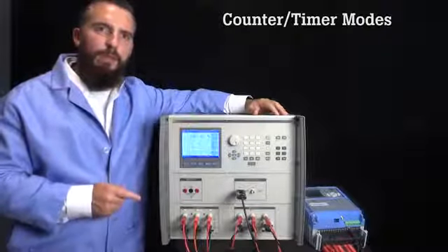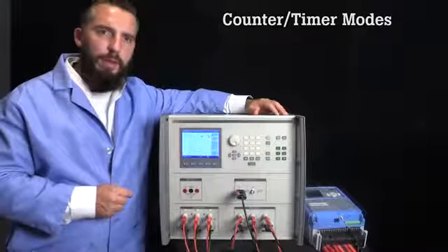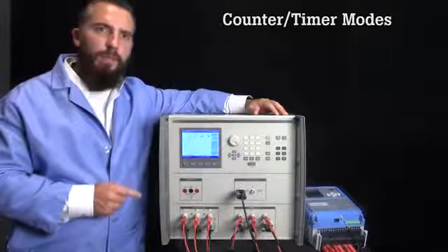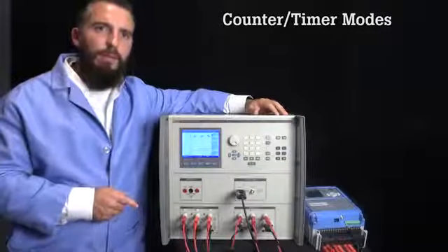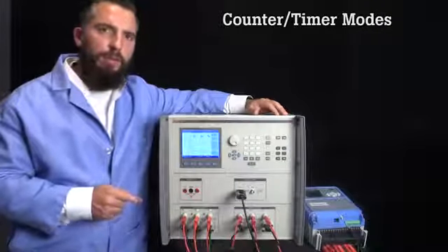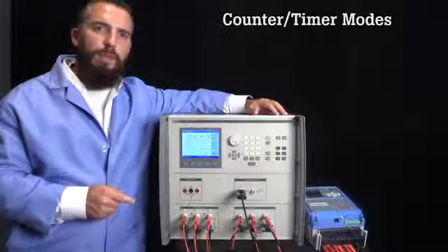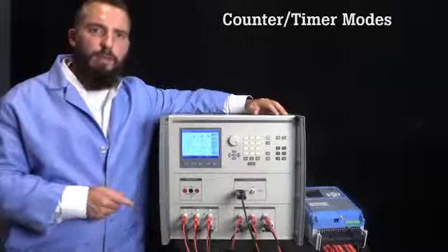This is very handy because the next time you will run a test at the same voltage, you may need 2 amps instead of 1. You simply change the current output on the 6003A while the voltage output is still active and powering the UUT.